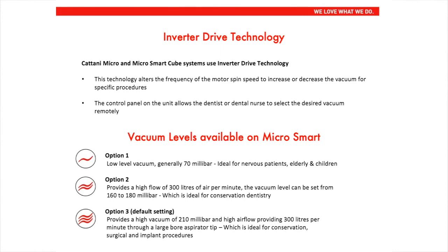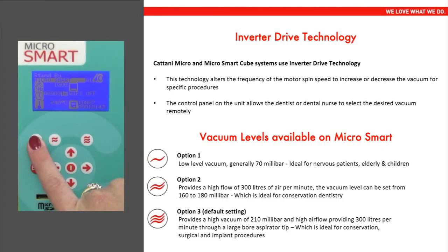Vacuum levels available on a Microsmart are: option 1, low level vacuum, generally 70 millibar, ideal for nervous patients, elderly and children. Option 2, this provides a high airflow of 300 litres of air per minute. The vacuum level can be set from 160 to 180 millibar, which is ideal for conservation dentistry. Option 3, this is the default setting. This provides high vacuum of 210 millibar and a high airflow of 300 litres of air per minute through the large bore aspirator tip, which is ideal for conservation, surgical and implant procedures.